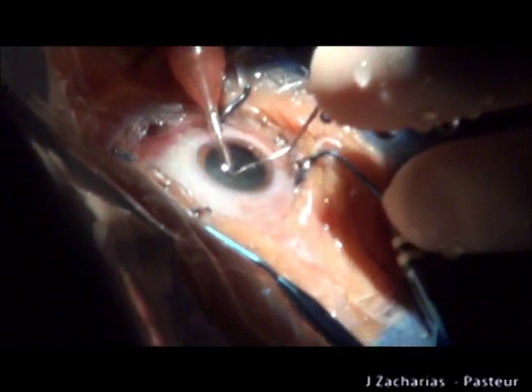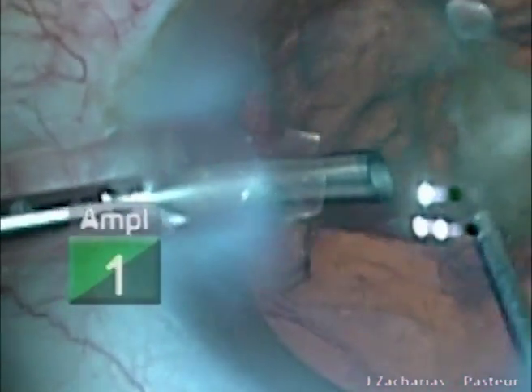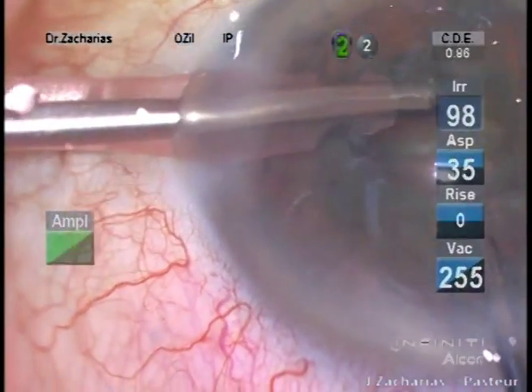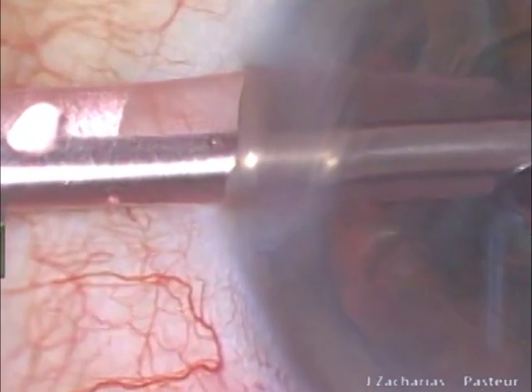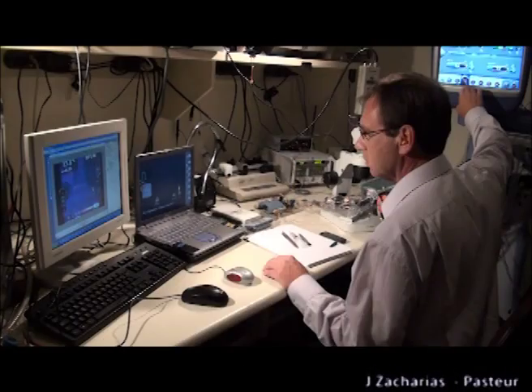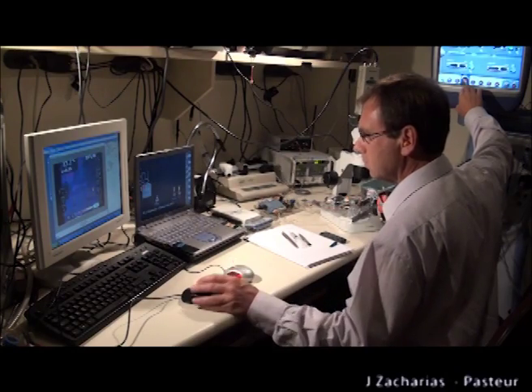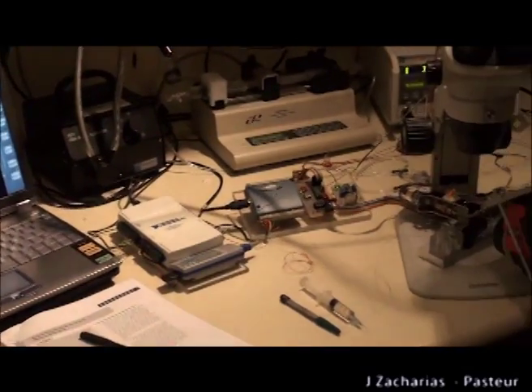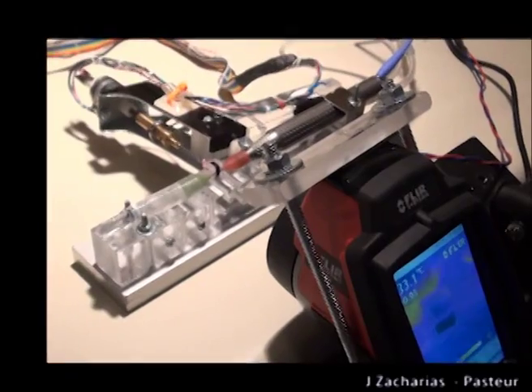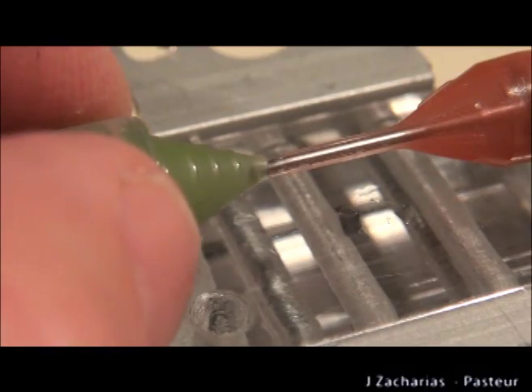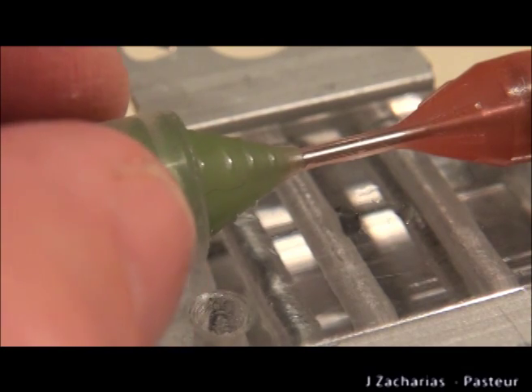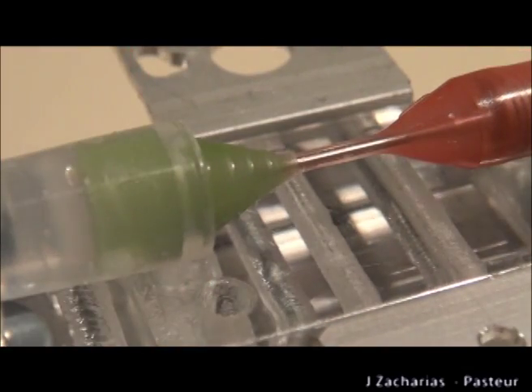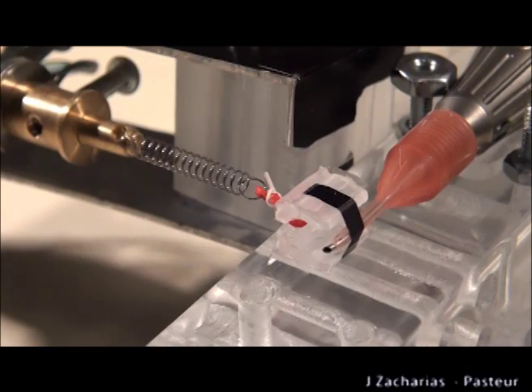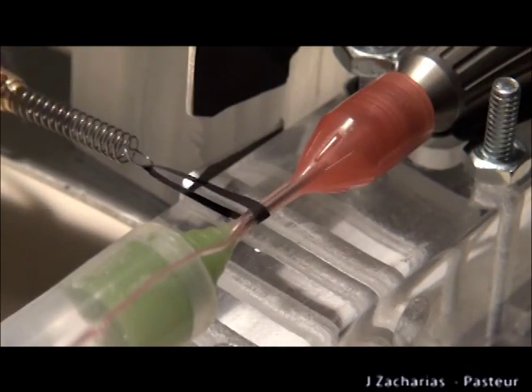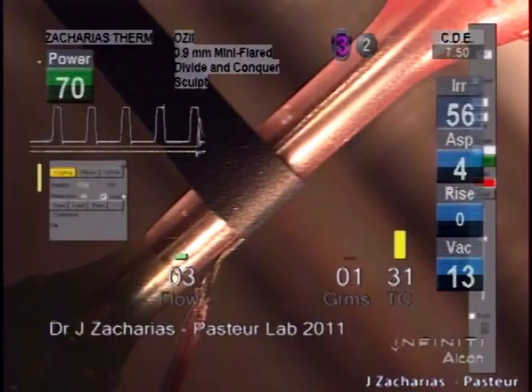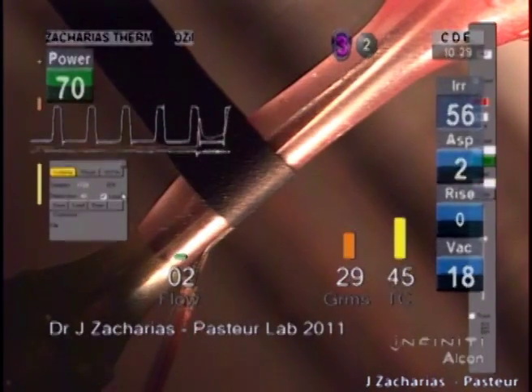Surgeons manipulating a handpiece will apply force against the incision walls with the vibrating probe. The impact of sleeve compression at incision level was evaluated for torsional and axial modes. A different computer-controlled system was built to examine the thermal response of the probe sleeve complex under controlled load conditions and flow restriction. A special array was implemented to accommodate the sleeve distal end, allowing flow without constriction of the incisional zone. Force was transmitted to the surface of the sleeve using a 2.2 mm strip of thin film, emulating stress conditions occurring during real surgery.